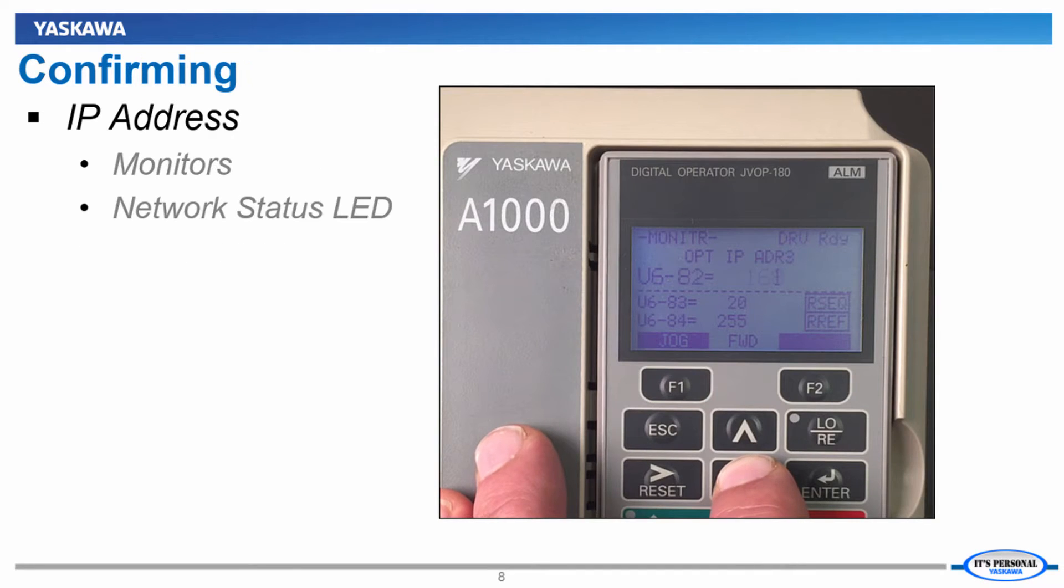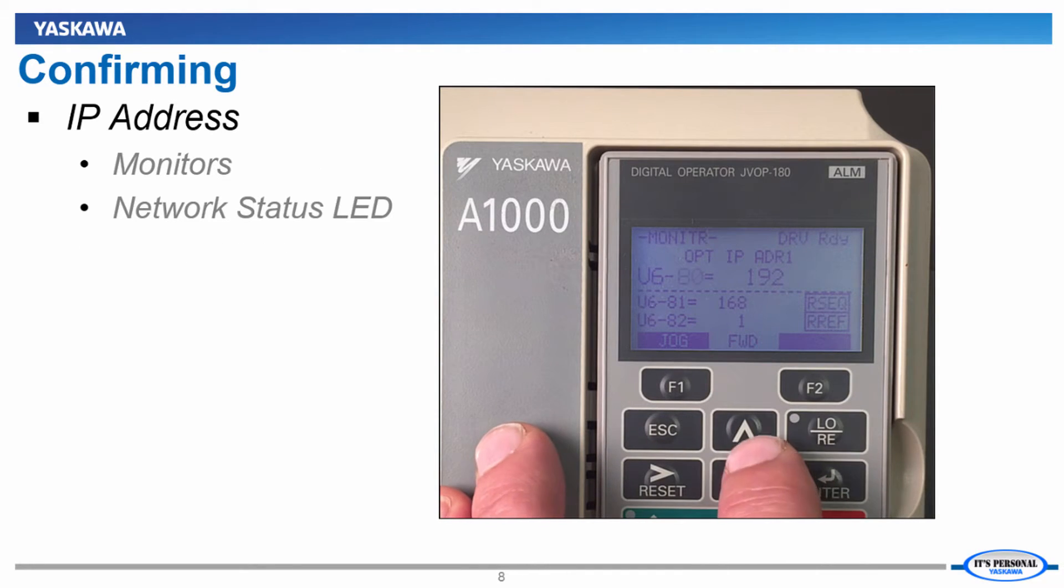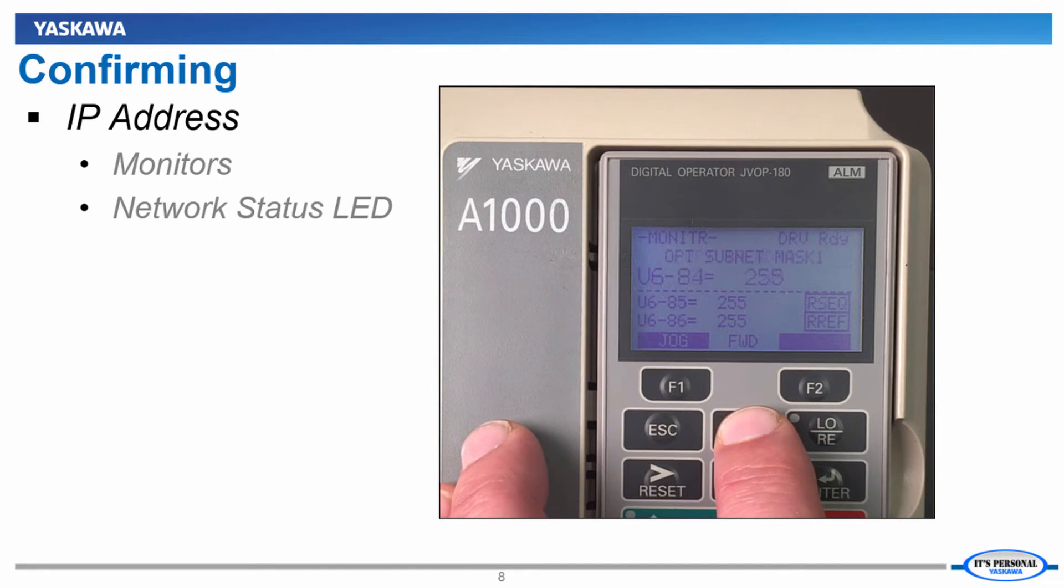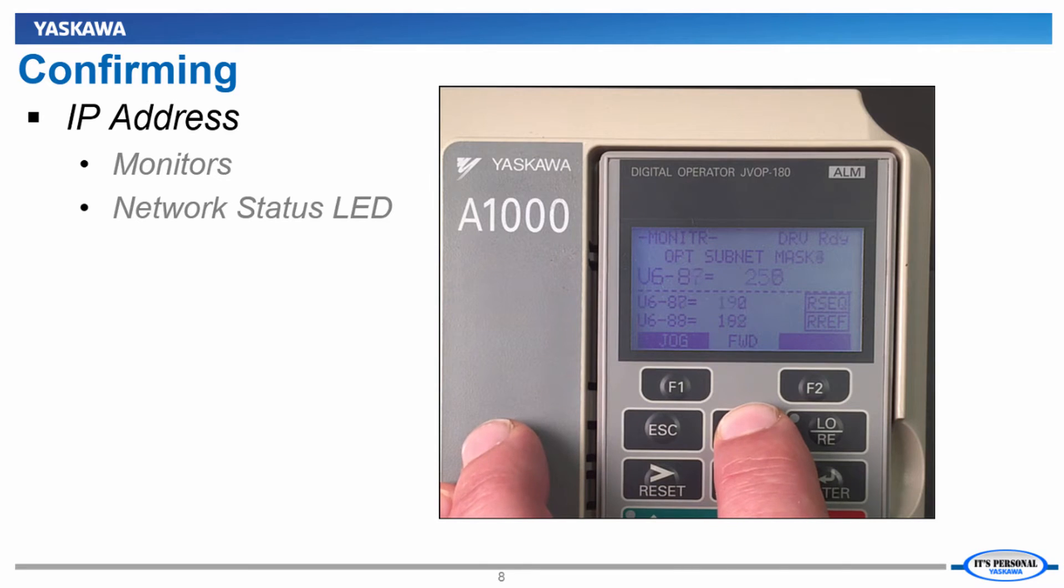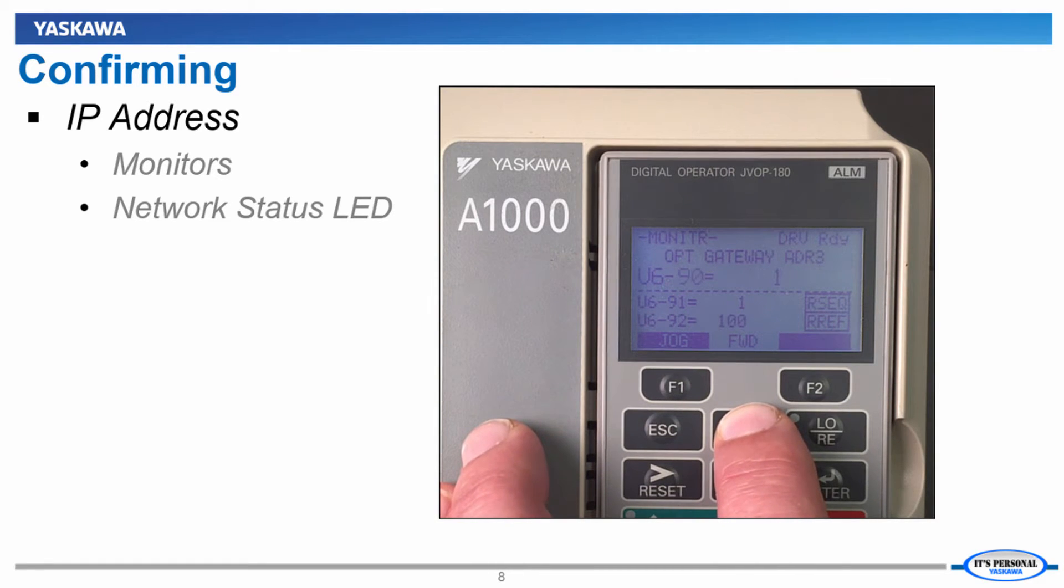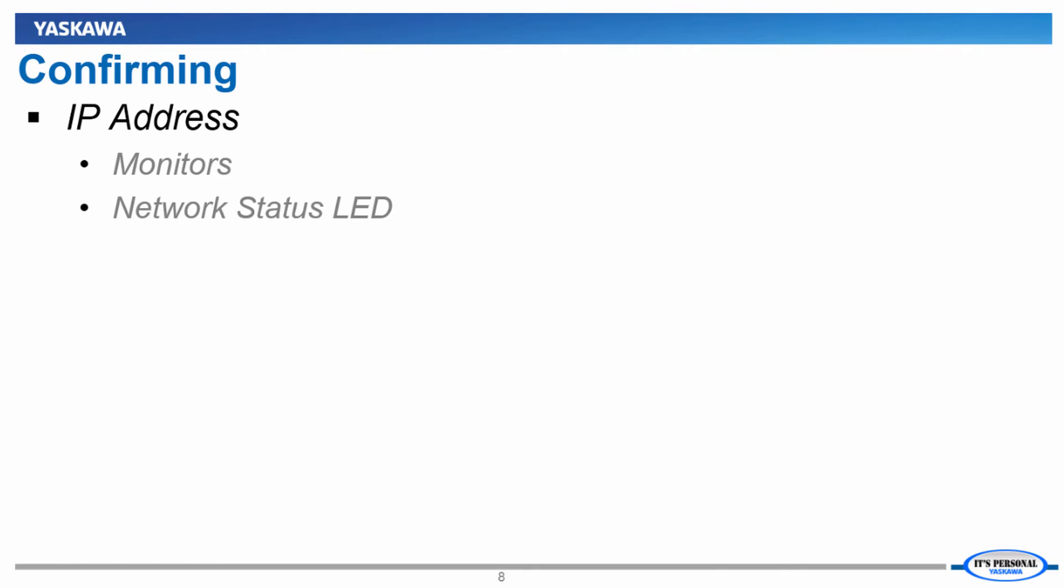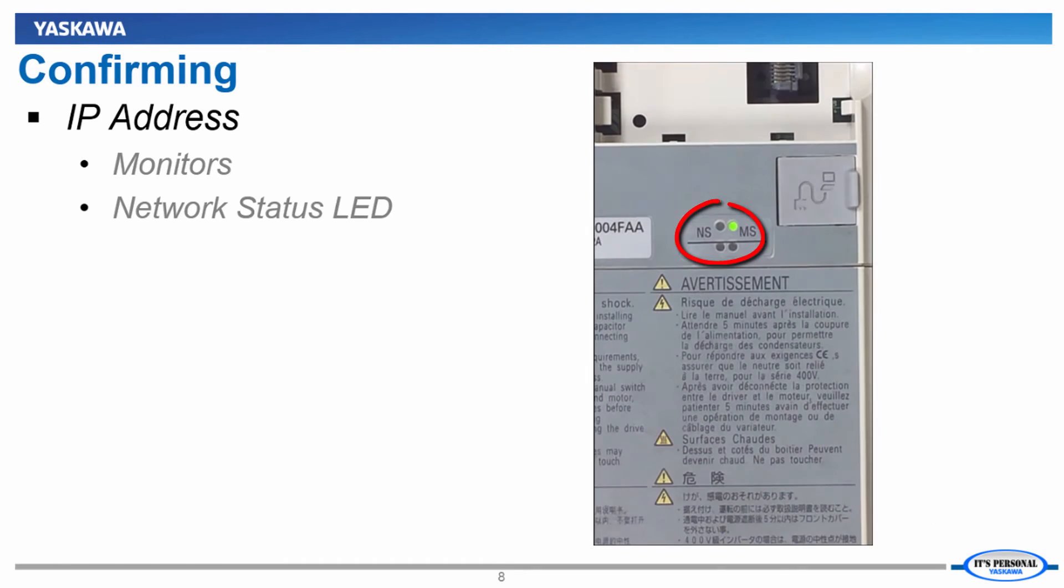To confirm our addresses have taken, we can use monitor U6-80 through U6-91 to check the values. These values will show as long as the option card is connected to another device via its Ethernet cable, which in our case is the PLC. Also, the network status LED on the option card should now glow a steady green.